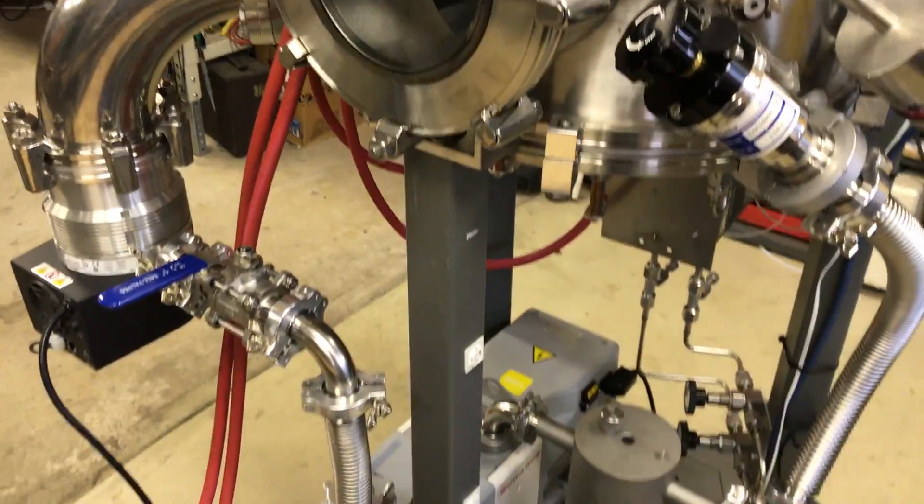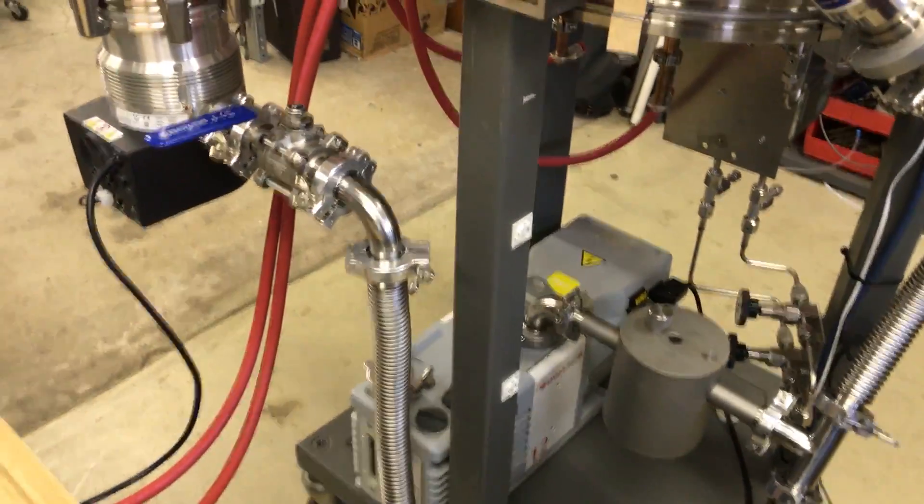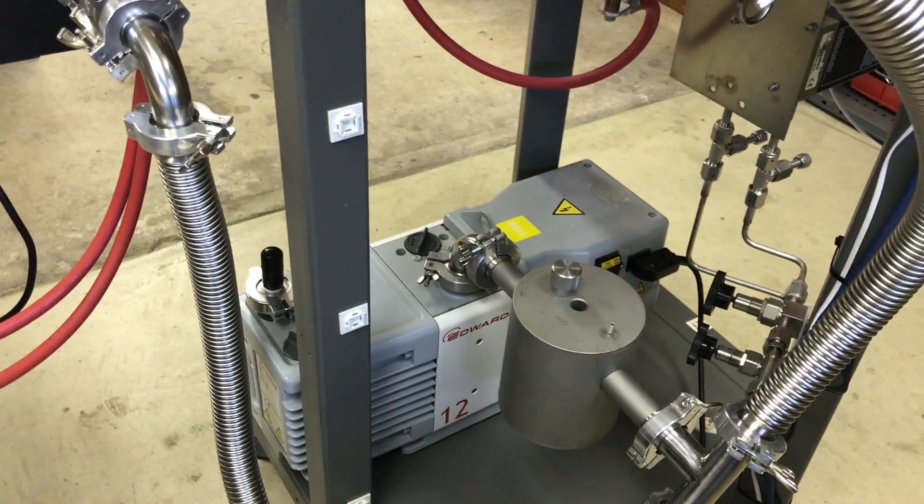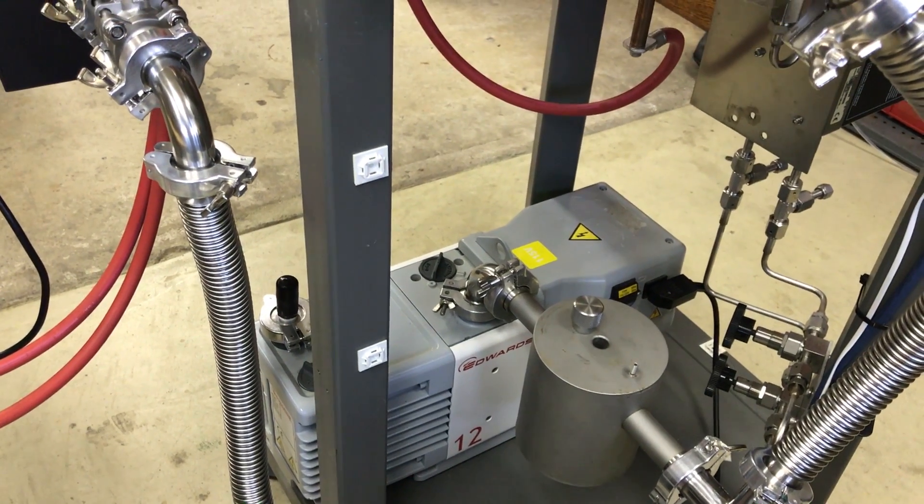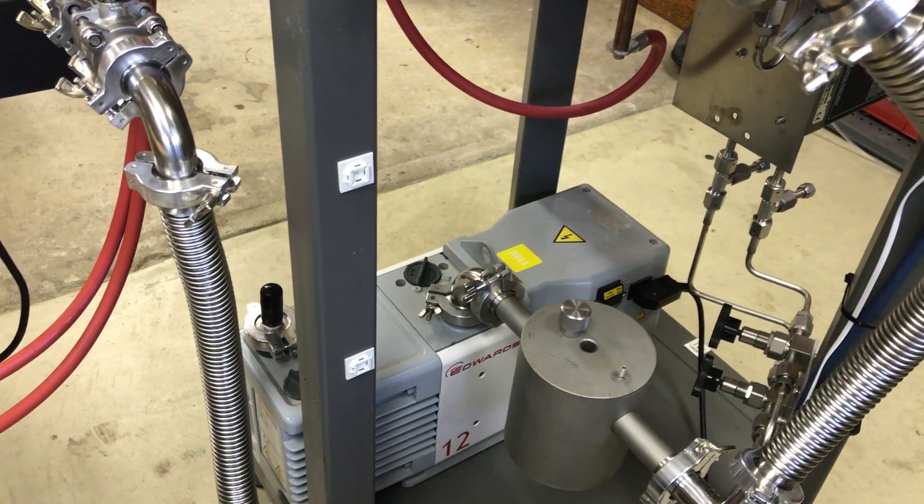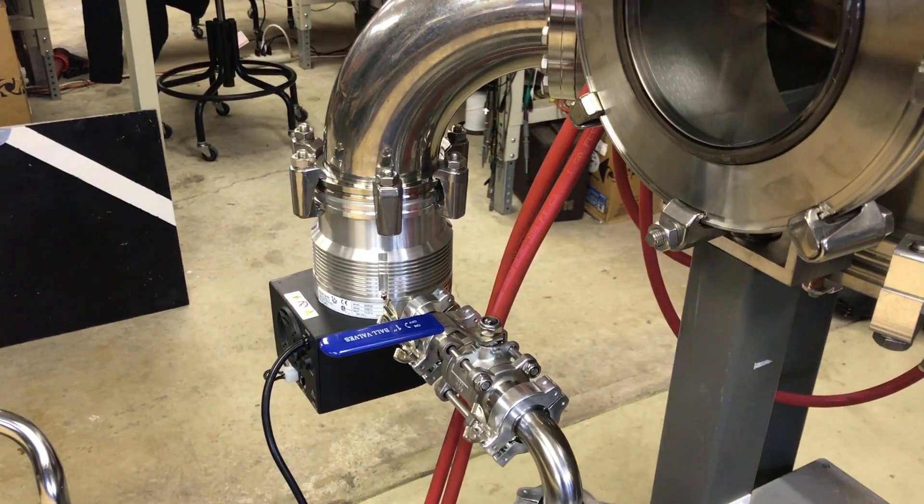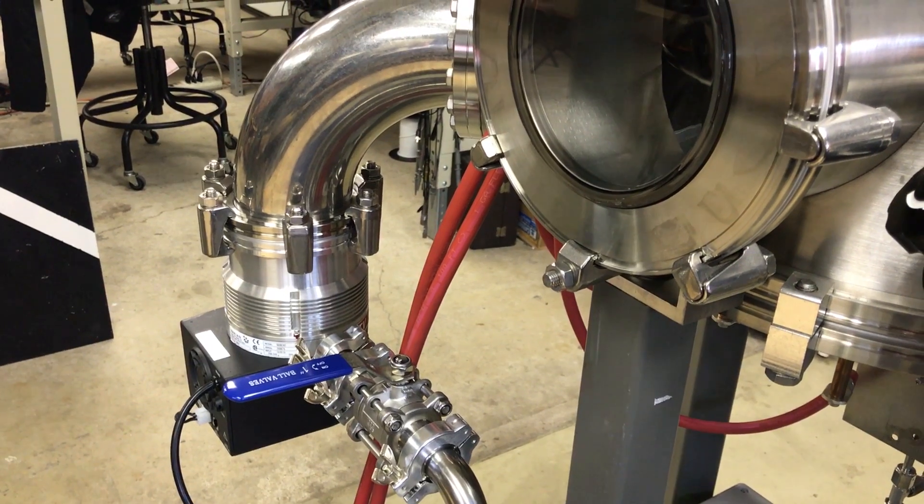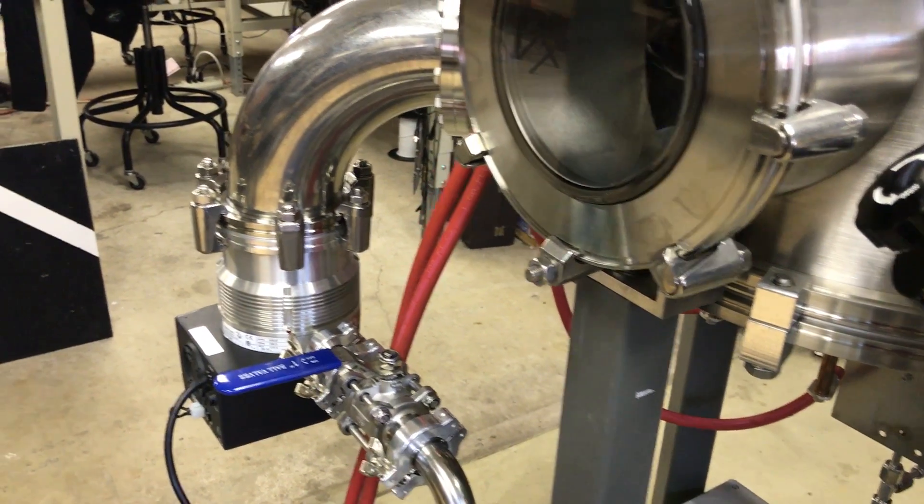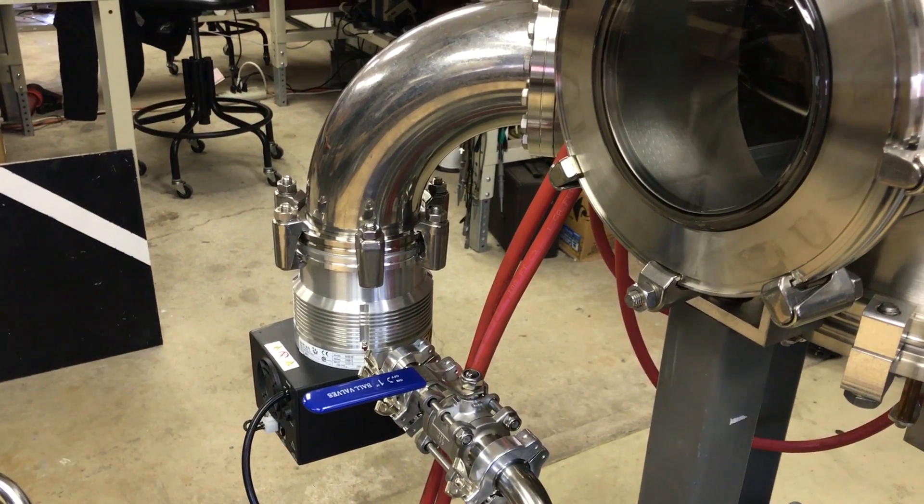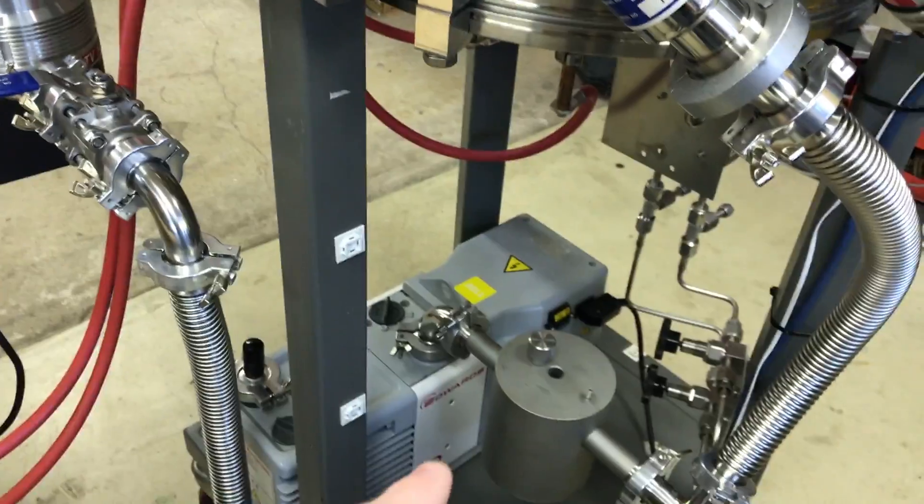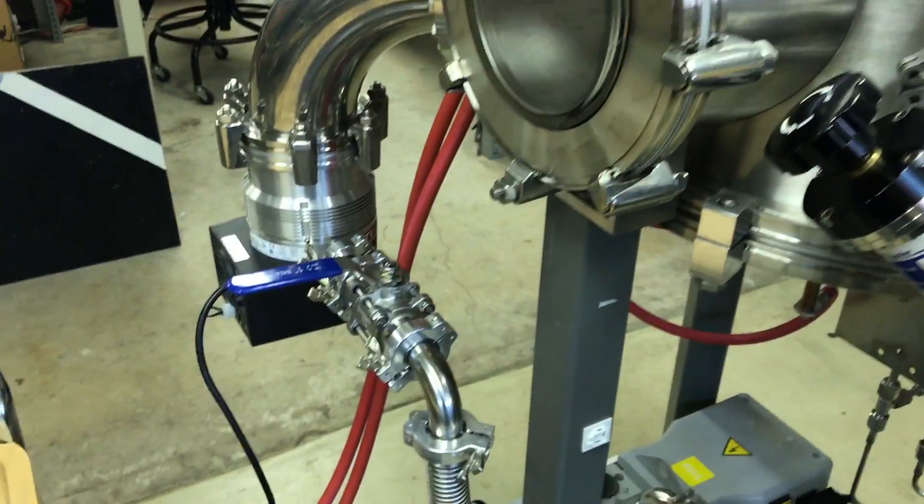Let's talk about pumps real quick. There's two big categories of pumps you'll need to get into very high vacuums. The main one is a mechanical pump. Down there is an Edwards No. 12 rotary vane mechanical pump. And that'll get me down to 1 times 10 to the minus 3 torr. And then I have a turbo molecular pump, which is a high vacuum pump. And then once the chamber is roughed down to 1 times 10 to the minus 3, this can get me to minus 6 to minus 7 range. But this cannot pump down from atmosphere.